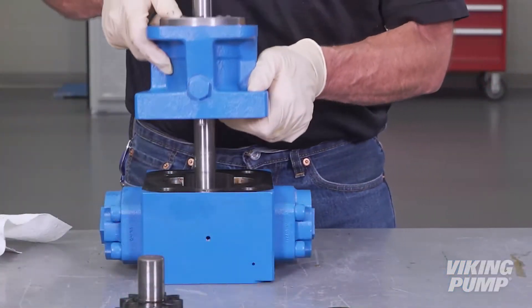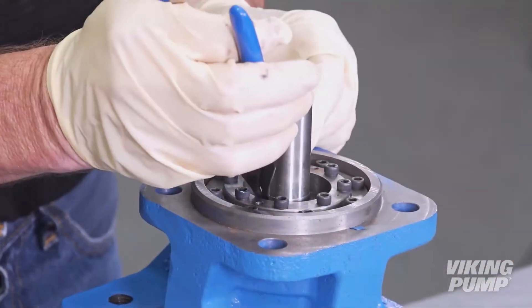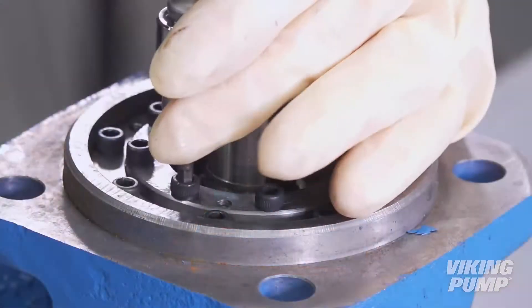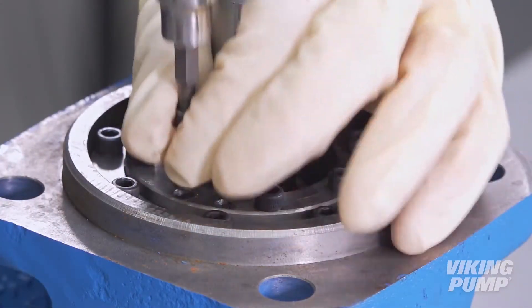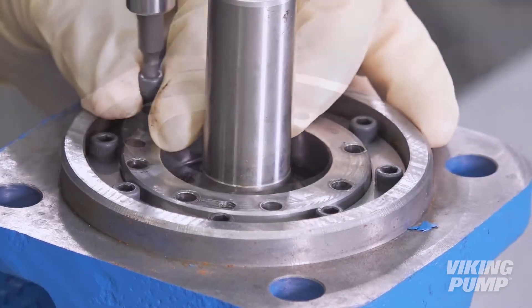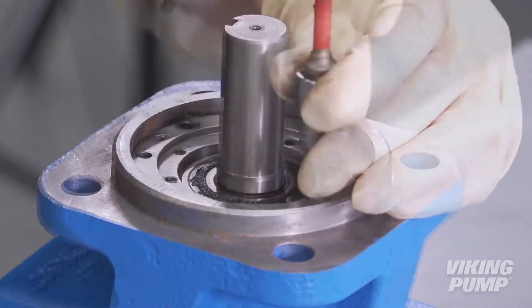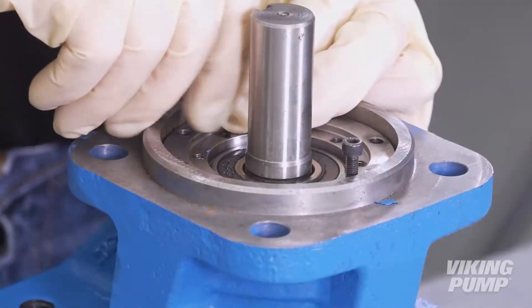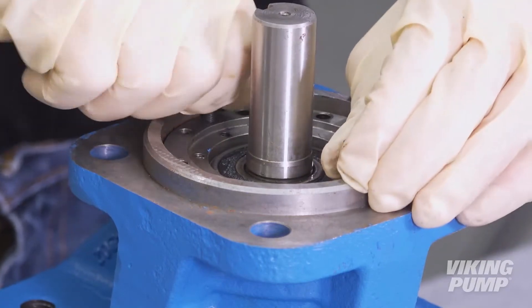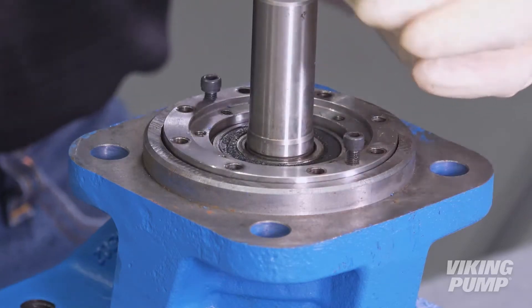Next, using the casing as a support fixture, orient the bracket into a vertical position to aid with seal removal. First, remove and discard the outer snap ring. Using a 3/16 inch Allen wrench, remove and discard the bearing end cap and seal holder cap screws. Set the bearing end cap aside for reassembly. To aid with seal removal, thread bearing end cap cap screws into the jack bolt holes located on the seal holder assembly. Alternate tightening these jack bolts to gently push the seal holder out.